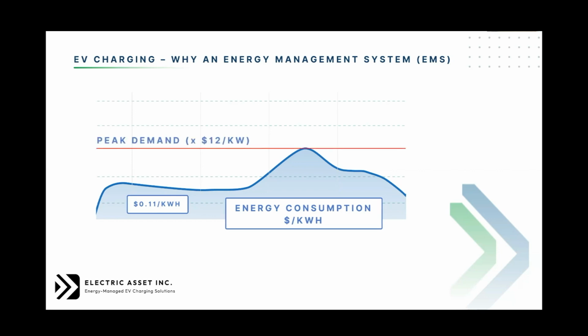Now, if you notice, the peak of this curve only lasts for a small period of time, but strata properties pay based on peak demand. This peak demand, the red line, is at the highest point it reached. It might have reached that point for 15 minutes during this one month, but that's the highest rate they take, and they charge you based on that high rate. Whatever the highest watermark or highest usage mark of that month, that's what you get billed on.